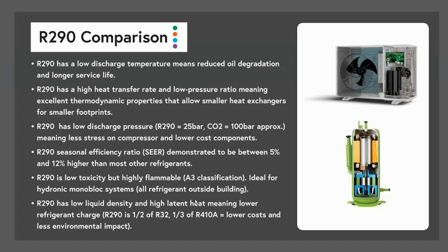Just to put it in perspective, a gas bottle for a barbecue is about 9 kilos of LPG. We strap 45 kilo bottles of LPG to the side of most houses, or many houses, in New Zealand, using that for cooking and home heating, and also hot water production using your Rinnai Infinity, that sort of thing. So that's almost 90 kilos. That's the maximum limit that can be attached to a residential house under the current building consent. And the largest R290 heat pump in our range contains 1.3 kilos of propane. So it's a very, very small amount compared to other uses of a similar fuel. So the risk of using propane for this in a sealed system is very low to non-existent.